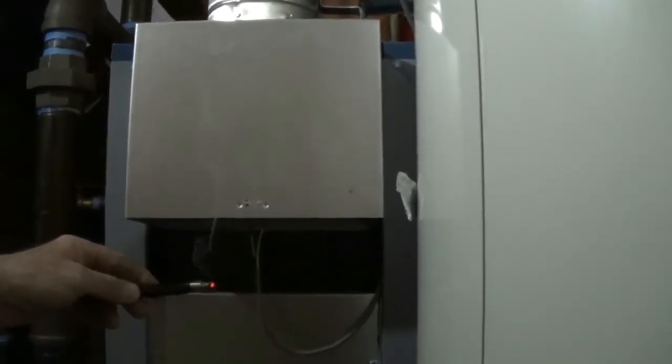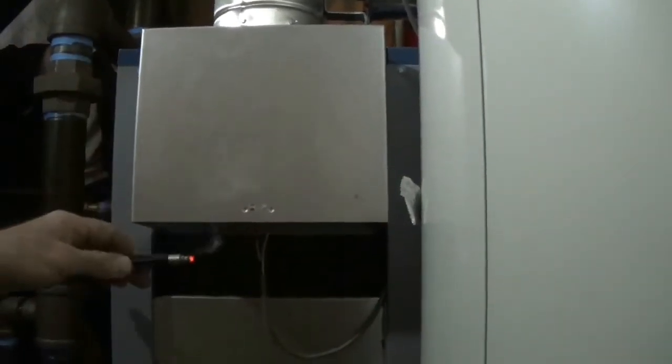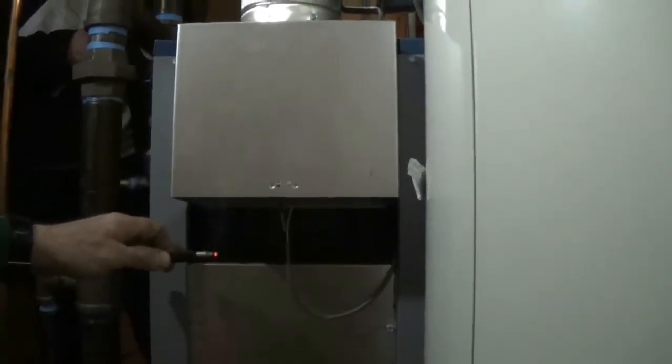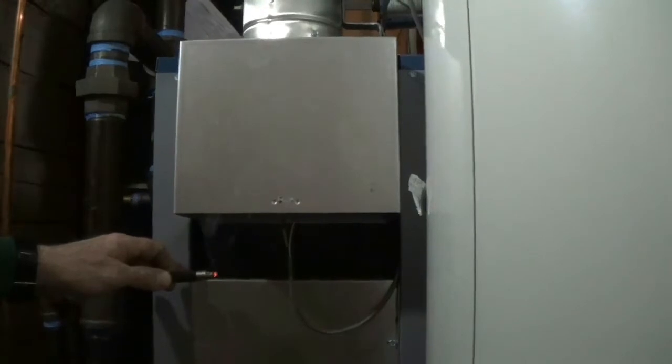Now, why does it have 60 seconds to pass spillage? So what will often happen is the equipment has to heat the flue up, the metal part and the chimney, to a certain degree, to get the draft to start up. So we give it 60 seconds to give it a fair chance. Sometimes you'll turn things on and it'll pass right away, right? And you could sit there for the other 60 seconds and it's still passing.